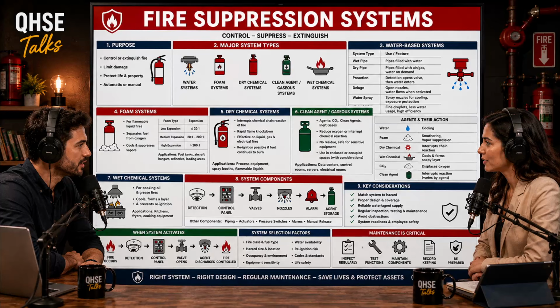If a worker spots a small fire in a trash can and they have to run 150 feet down a hallway, navigate around pallets to grab the extinguisher, figure out the pin, and run 150 feet back. A solid 60 to 90 seconds have elapsed. And in 90 seconds, that small trash can fire has likely ignited the curtains and the ceiling tiles. It has transitioned from the incipient stage into the free-burning stage. The radiant heat is now too intense to approach. Attempting to fight it with a 10-pound extinguisher is deadly at that point.